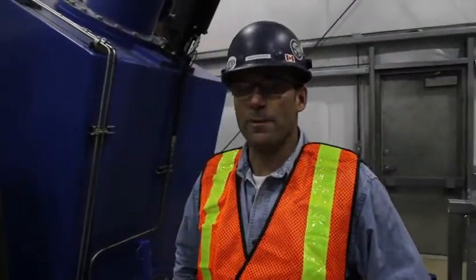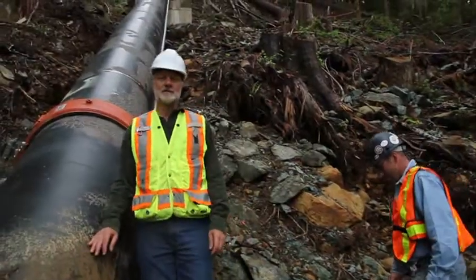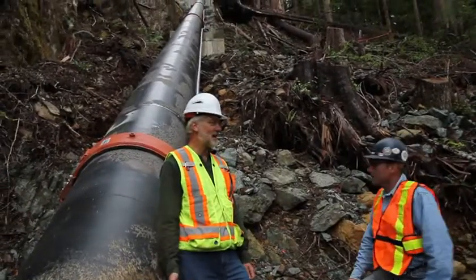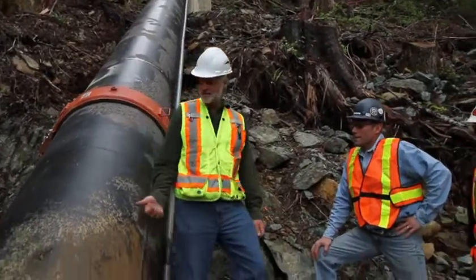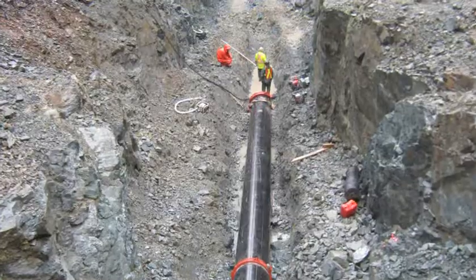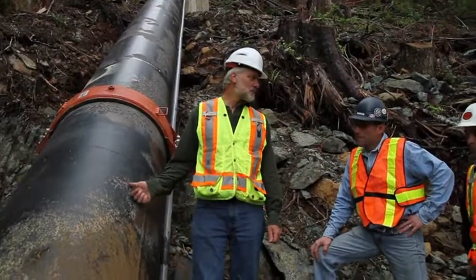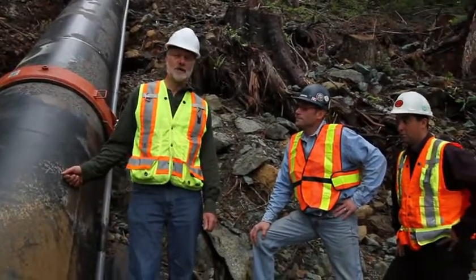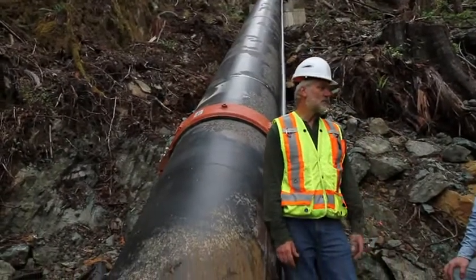I prepared the pipe for both the welding and for the Victaulic Couplings. This is the upper overland section of the Canute Creek Hydro Project. It's a five and a half megawatt project. It's one-meter penstock, steel penstock from the top to the bottom. We've got 476 meters of head. On this project, a lot of this pipe is used pipe — it was used pipe out of Alberta. We recoated it and then we used the Victaulic Couplings on it.